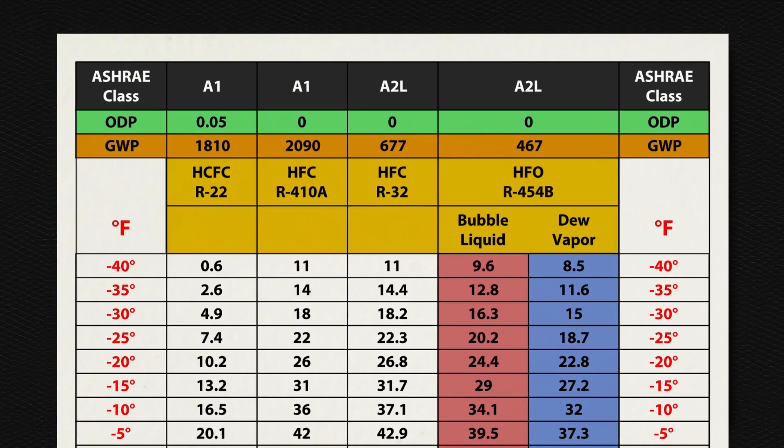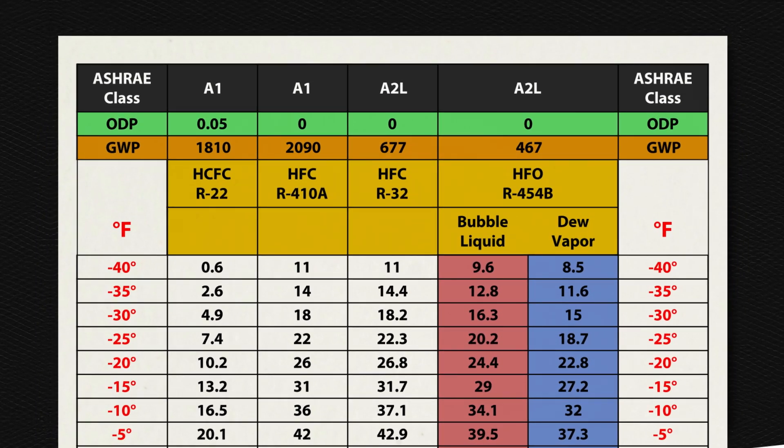On the left of the PT chart are the saturated temperatures, or boiling point, and in the body of the PT chart are the pressures for specific refrigerants. Remember, the saturated refrigerant will remain constant temperature at a given pressure.